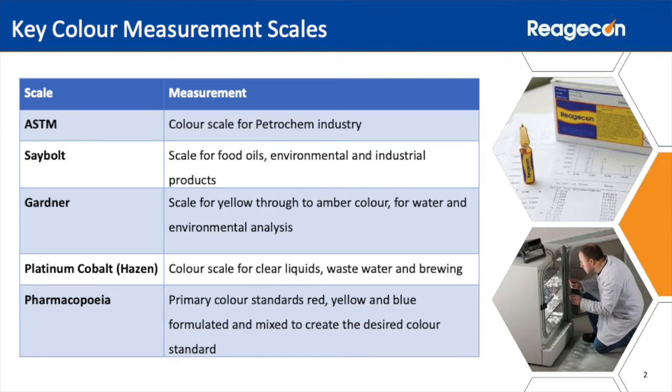Pharmacopoeia methods for colour assessment of pharmaceutical solutions are based mostly on a visual comparison. Starting with primary colour liquid standards red, yellow and blue, formulated as per the pharmacopoeia, dilutions and mixes of these primary colours are made to give colour standards such as brown and green, and in turn produce the working standards.